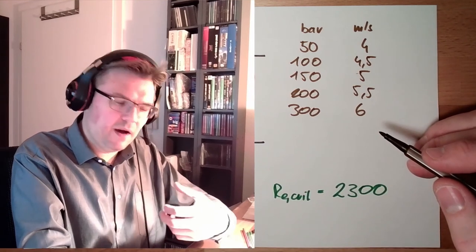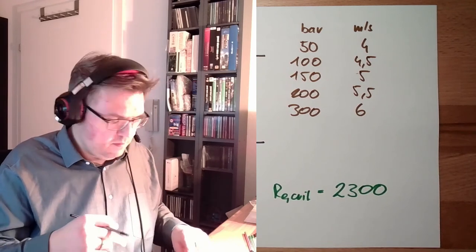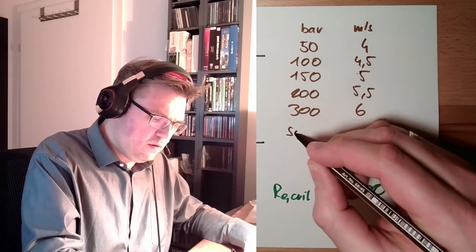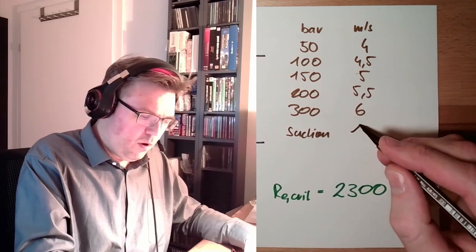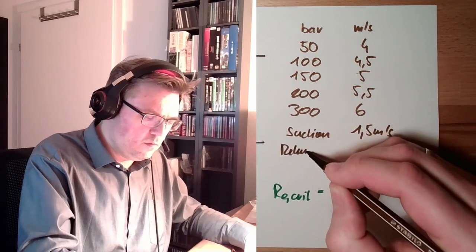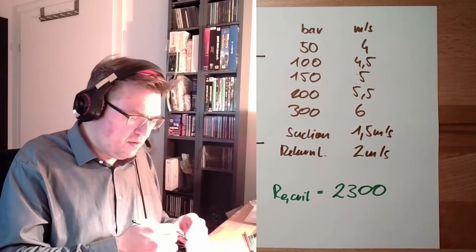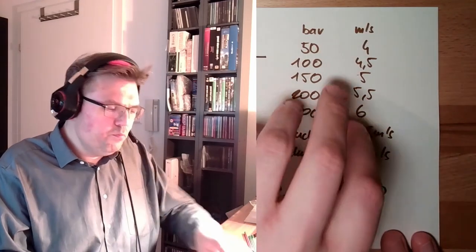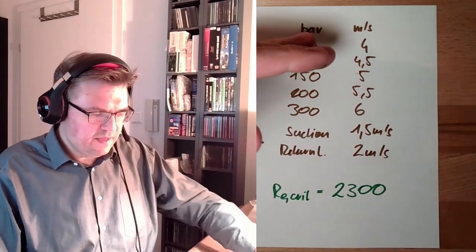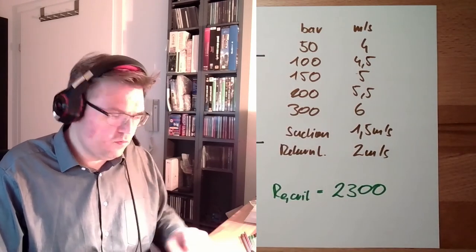If there is the suction line of the pump. So, where the pump is sucking in the oil. There is not much pressure at all. Even it is below the ambient pressure, of course. So, the suction line, we are at around 1.5 meters per second. And at the return line, we are around 2 meters per second. So, this is the usual speeds or the maximum speeds, the critical speeds to prevent turbulent flow. Like I said, the higher the pressure, the higher the speed can go. The lower the pressure, the lower the speed must be to stay in laminar.